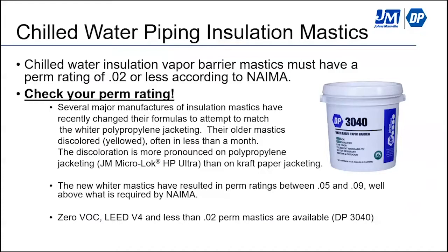The problem is that with the reformulation to make their sealants whiter, the perm rating is well above what is allowed for NAIMA for chilled water piping. The perm ratings have gone from 0.016 to 0.05 to 0.09, and again, that's well above what NAIMA allows.